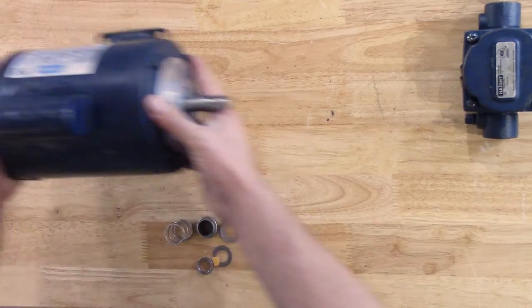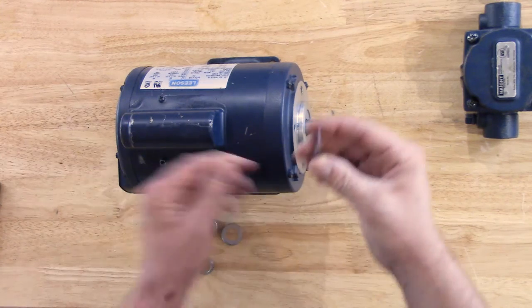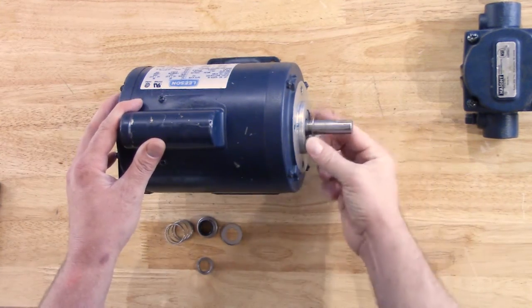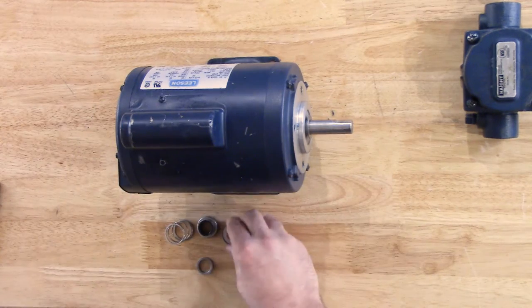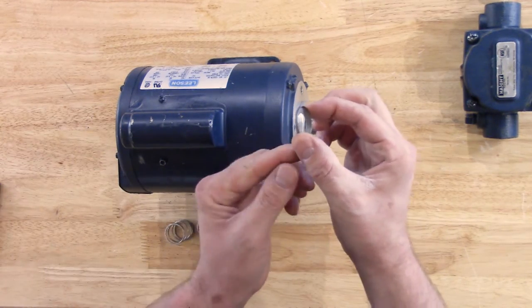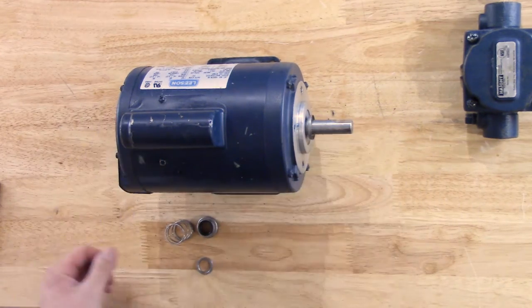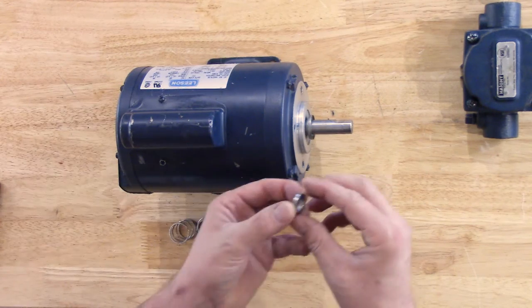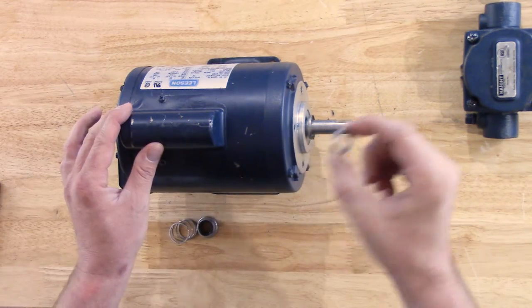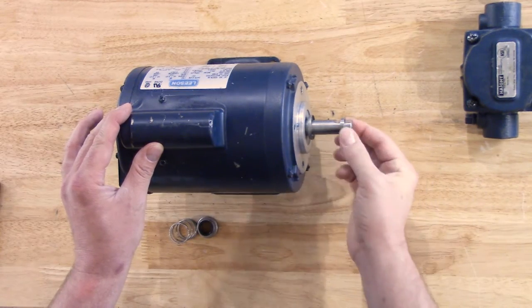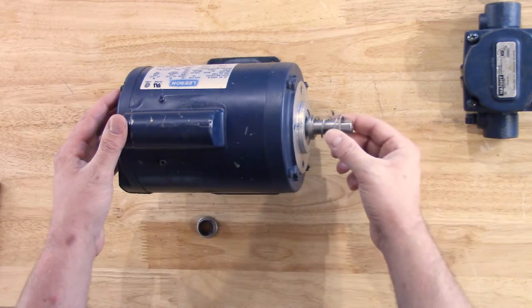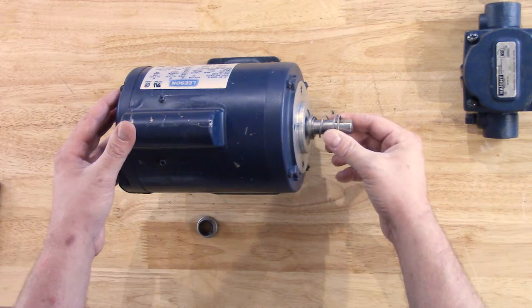Now that we have our pump put back together, we'll set this off to the side for a moment and bring our attention back to the motor. Here, we will start to put the seal kit back together by starting with the flat washer going on to the motor first. Then we will go with our recessed washer with the recess facing towards the pump. Now we can go on with our spring spacer as well as our spring that goes over that spacer and inside of that recessed washer that we just put on.